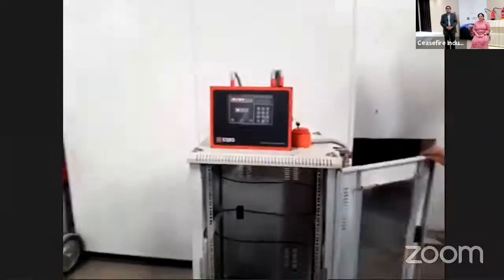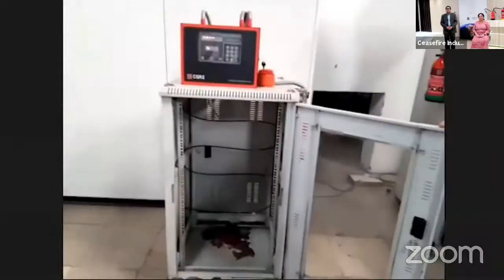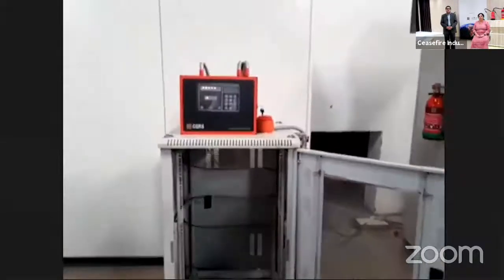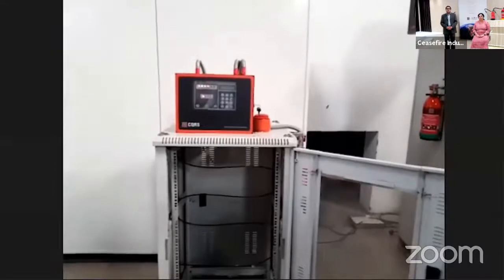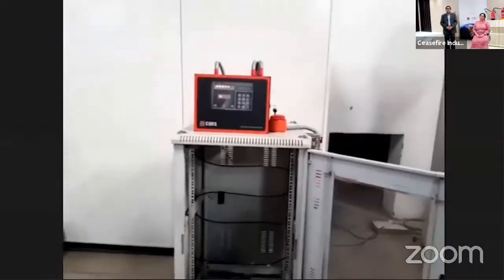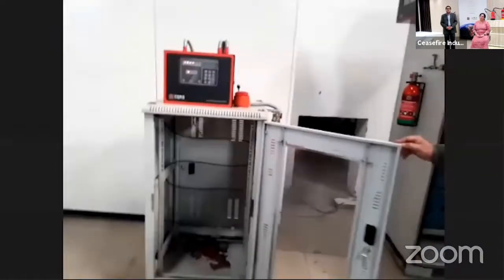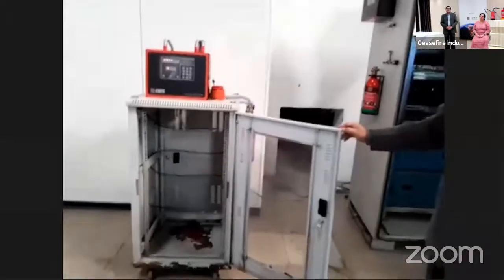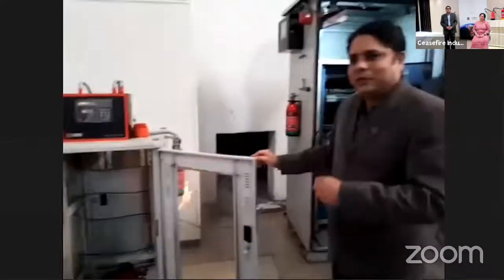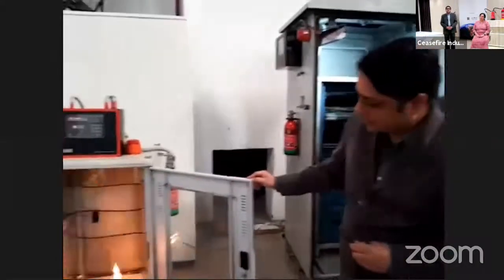Again, we are simulating a fire inside. Let's light a fire. So in the indirect system, the discharge will happen from the nozzles above, through a separate pipeline. The tube will just detect, depressurize, and open the valve.